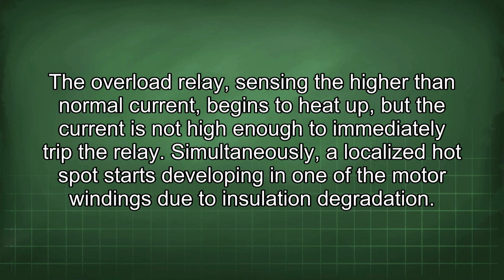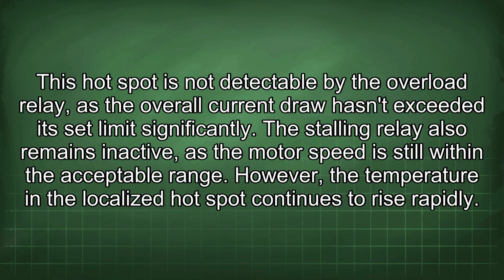Simultaneously, a localized hotspot starts developing in one of the motor windings due to insulation degradation. This hotspot is not detectable by the overload relay, as the overall current draw hasn't exceeded its set limit significantly. The stalling relay also remains inactive, as the motor speed is still within the acceptable range. However, the temperature in the localized hotspot continues to rise rapidly.